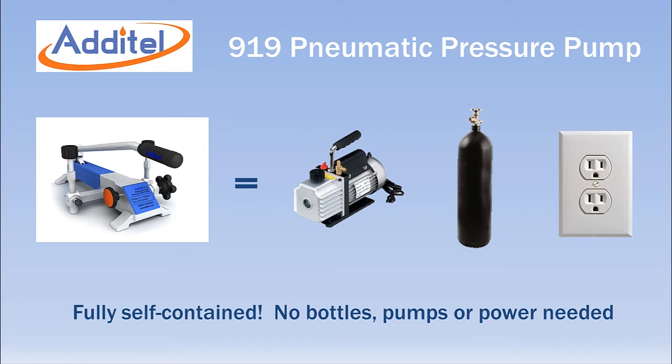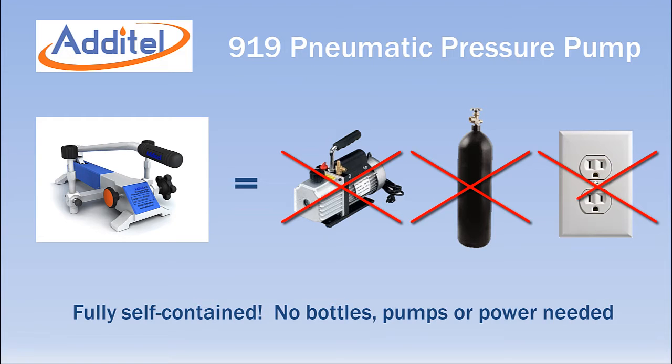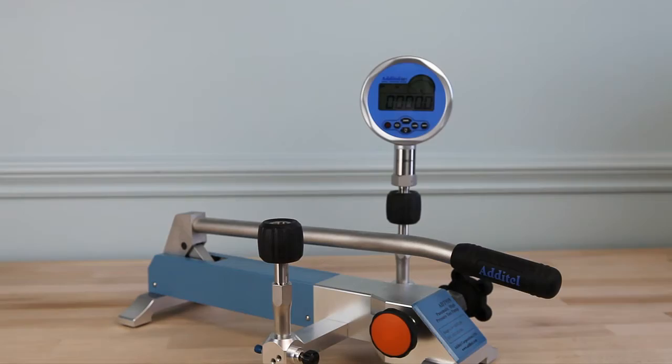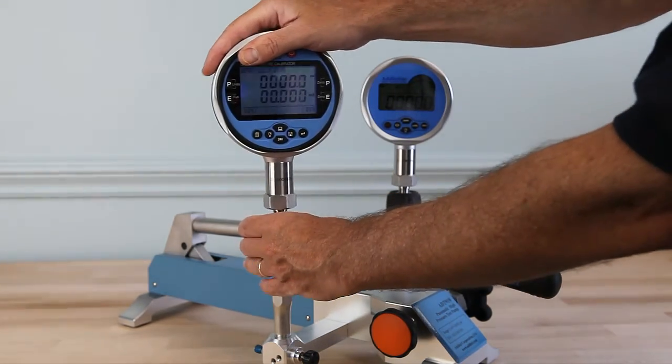Calibrations with the 919 do not require bulky gas cylinders or external pressure sources of any kind. The pump is fully self-contained and requires no power. All Additel pneumatic pressure pumps include two hand-tight NPT or BSP quick connections that do not require any tools or thread sealant for leak-tight operation.